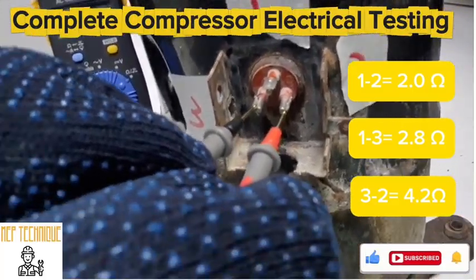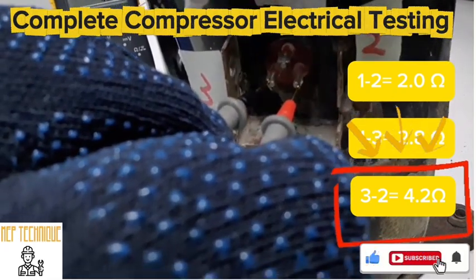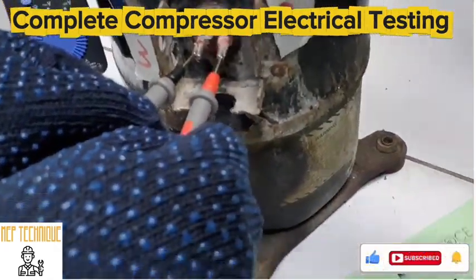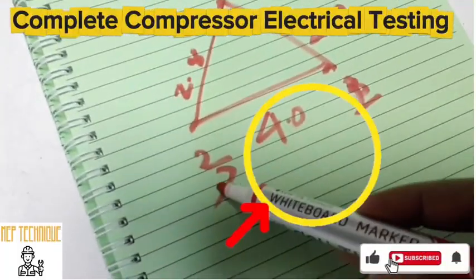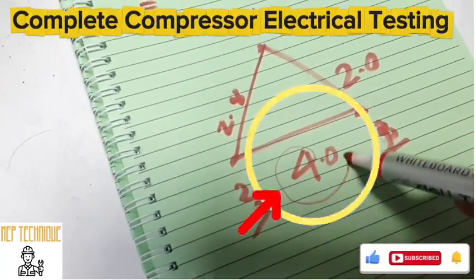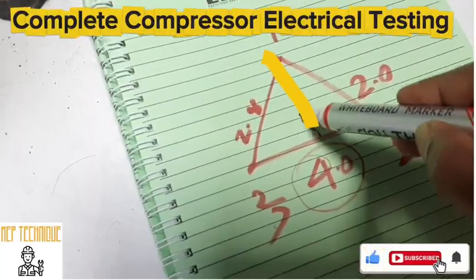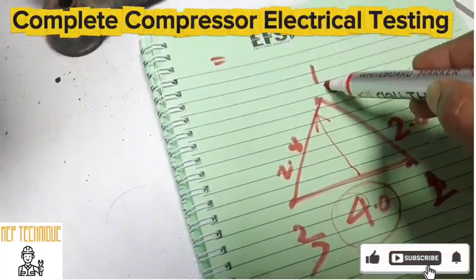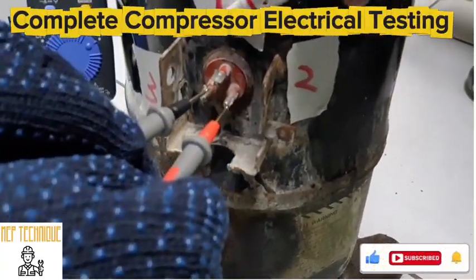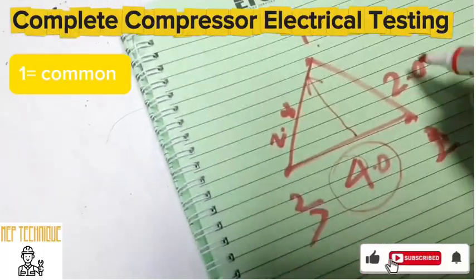So the resistance between 3 and 2 is the highest, about 4. Then the opposite terminal, 1, is common. So 1 is common.